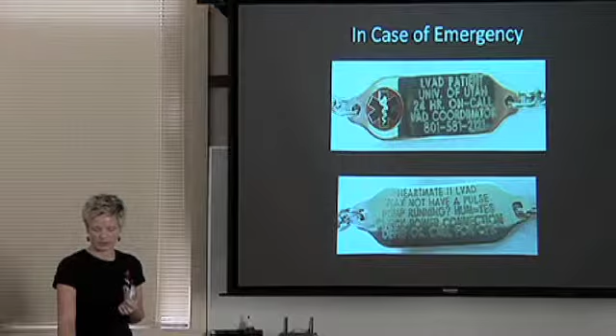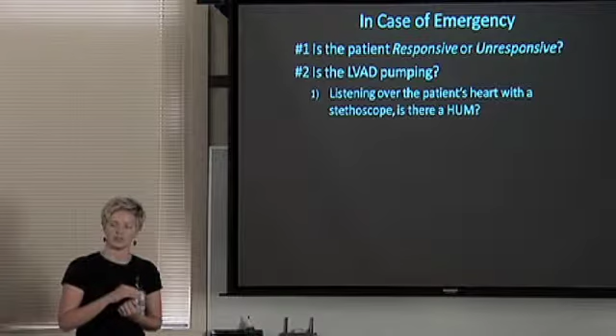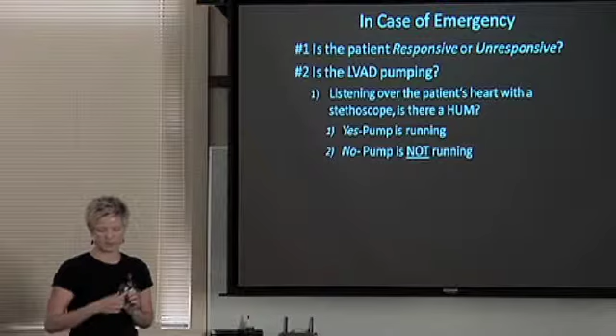So if you came across somebody that was unresponsive with an LVAD, or you yourself are, the first thing is to find out, is the patient responsive or unresponsive, and if there are alarms going on. Is the LVAD pump running? Listening over the patient's heart with a stethoscope, is there a hum? If you don't have a stethoscope and you just lay your head on the patient's chest, you will hear the pump whether it's humming or not humming. If the pump's humming, it's running. If it's not humming, it's not running.